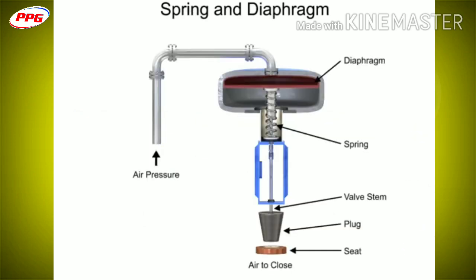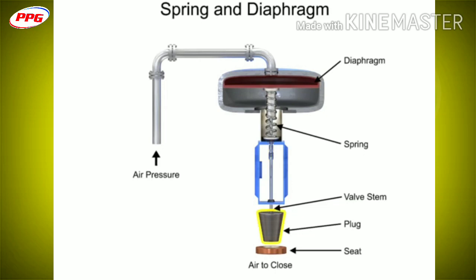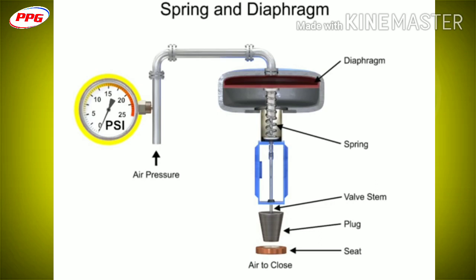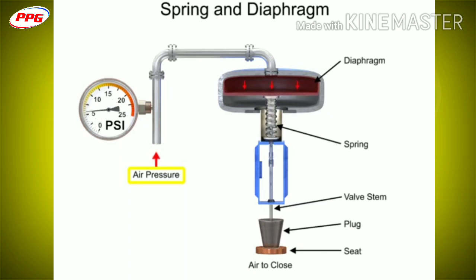The spring and diaphragm actuator uses a spring and a diaphragm to move the valve stem and plug. A 15 PSI pneumatic signal enters the housing at the top of the actuator. As pressure is exerted on the diaphragm, a downward force is applied against the spring which moves the restrictor.